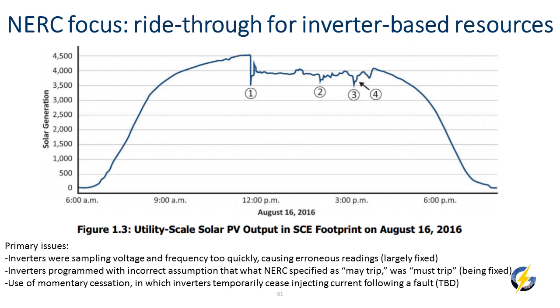There was a section of that standard that said it is permissible to trip your unit in this area, and people interpreted that standard as saying you must trip if you have this type of voltage excursion, which obviously contributed to this problem. Then finally, some inverters are programmed with a setting called momentary cessation, where the resource stops injecting current for a short period when there's a disturbance on the grid.